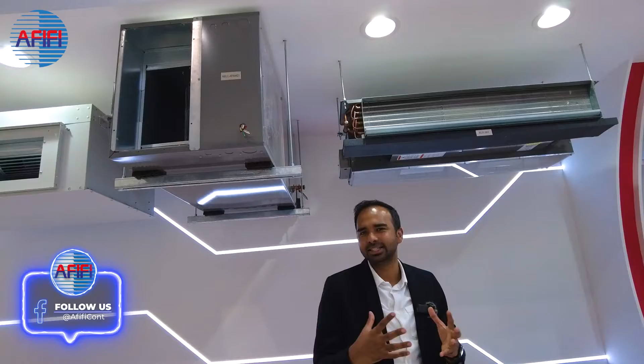This unit has 2 different chassis arrangements. Up to 3 ton, it's a blow through, which means the coil is in the front. Yeah, so that's only up to 3 ton. Above 3 ton, it's similar to that. The blowers come in front, it becomes a draw through.